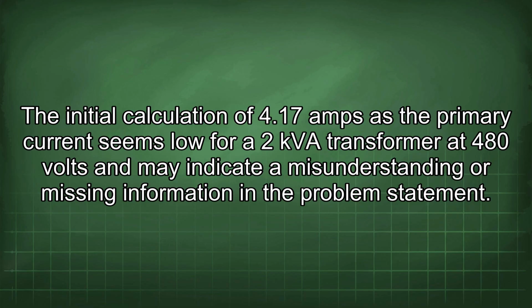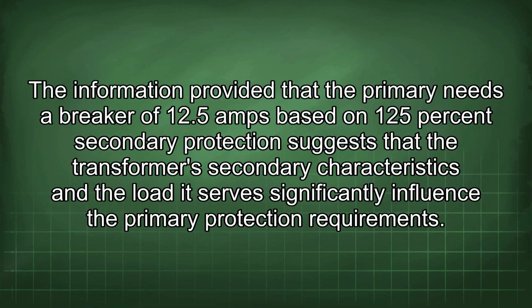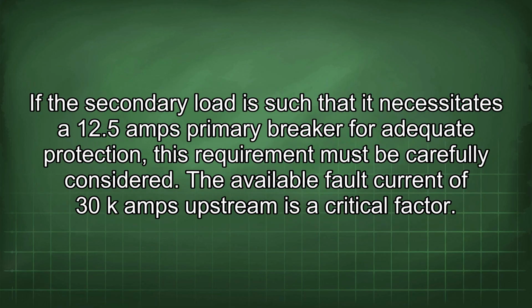The initial calculation of 4.17 amps as the primary current seems low for a 2 kVA transformer at 480 volts and may indicate a misunderstanding or missing information in the problem statement. The information provided that the primary needs a breaker of 12.5 amps based on 125% secondary protection suggests that the transformer's secondary characteristics and the load it serves significantly influence the primary protection requirements.